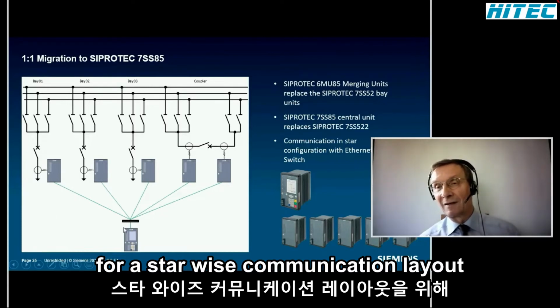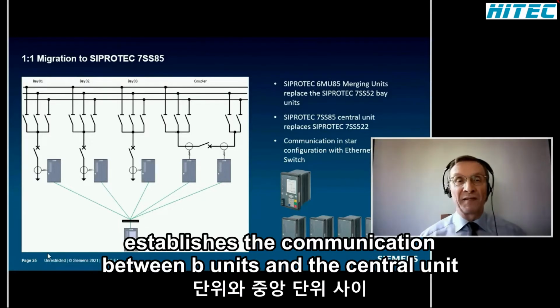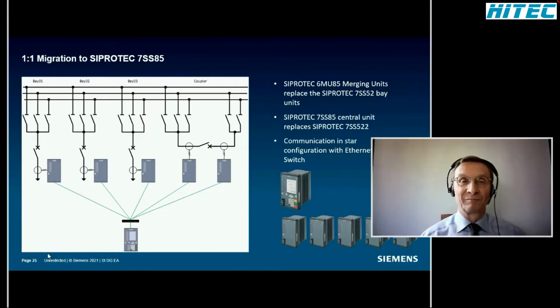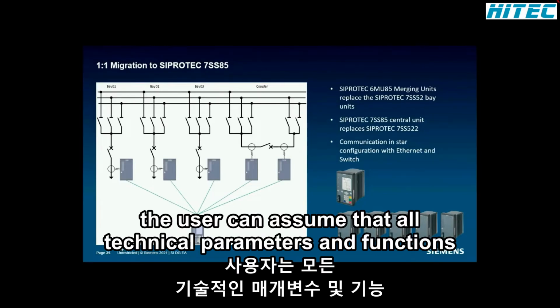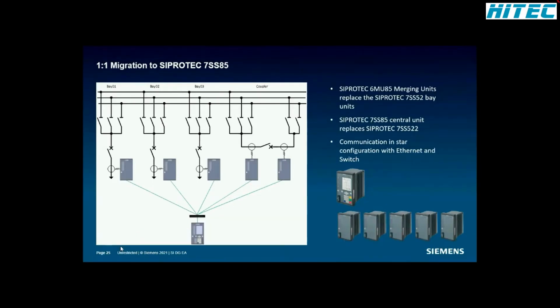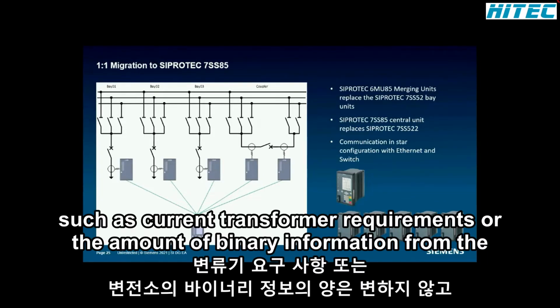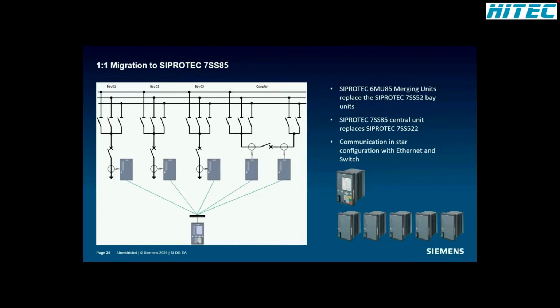For a starwise communication layout, an Ethernet switch together with fiber cables establishes the communication between bay units and the central unit. The user can assume that all technical parameters and functions, such as current transformer requirements or the amount of binary information from the substation, remain unchanged. Well, that's it so far for the successor application. Now let's talk about the more.